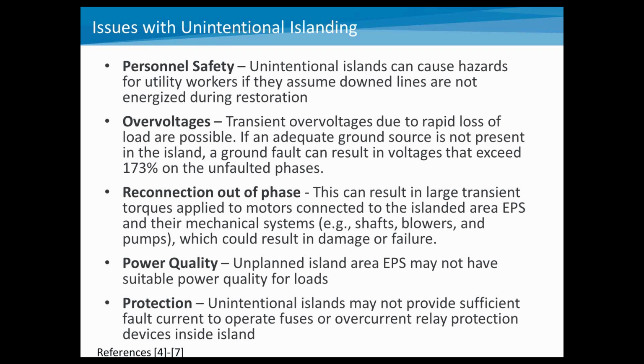And then power quality. Within any unplanned island, your distributed generation may not be able to provide suitable power quality for the loads. And then finally, protection issues. If you have an unintentional island, you may not be able to provide enough fault current, for example, to operate fuses or overcurrent relay protection inside the island. And so your protection systems may need to be adjusted. There's a variety of references you see on the bottom and then listed at the back end of the presentation.